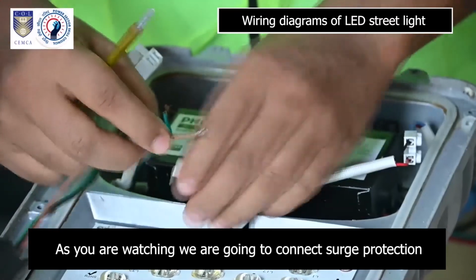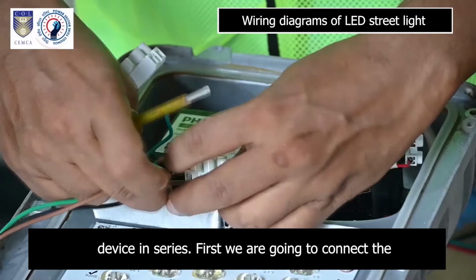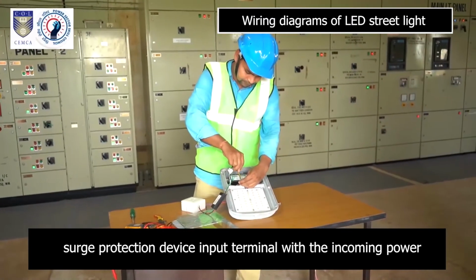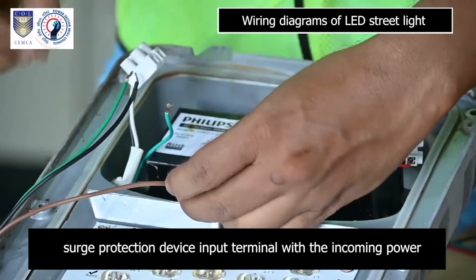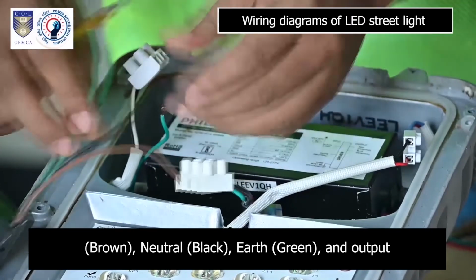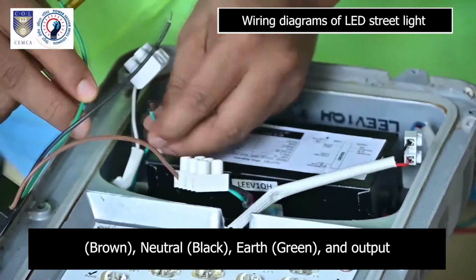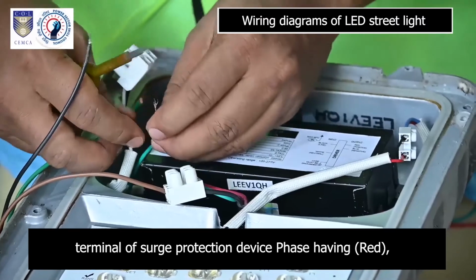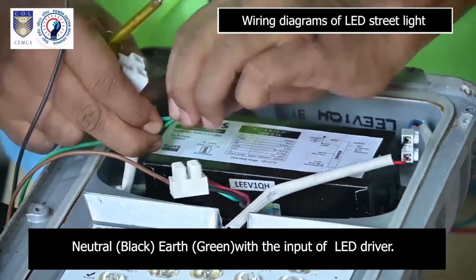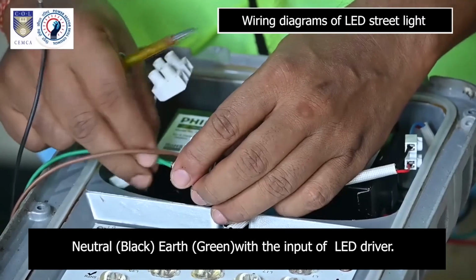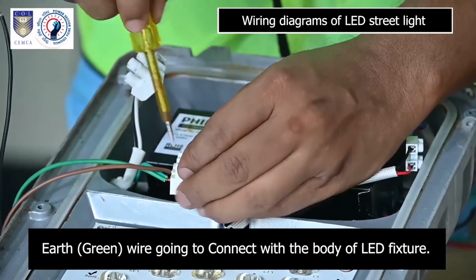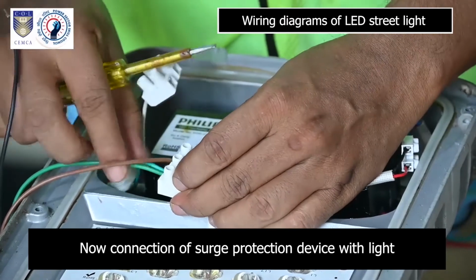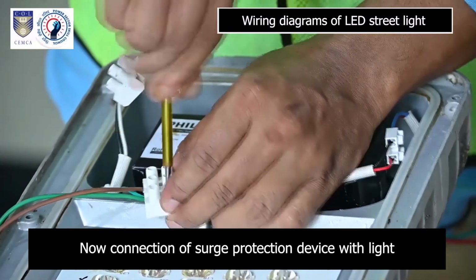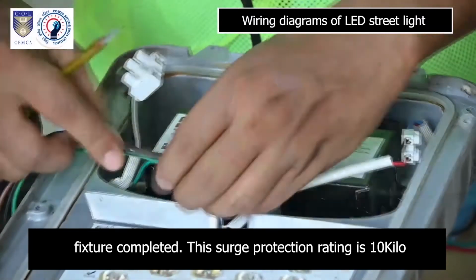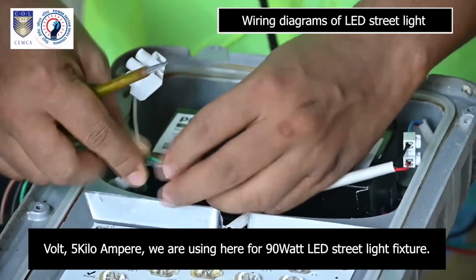As you are watching, we are going to connect surge protection device in series. First, we are going to connect the surge protection device input terminal with the incoming power supply terminal having 3-wire phase brown, neutral black, earth green, and output terminal of surge protection device phase red, neutral black, earth green with the input of LED driver. Earth green wire is going to connect with the body of LED fixture. Now, connection of surge protection device with light fixture is completed. This surge protection rating is 10 kV, 5 kA. We are using here for 90 watt LED street light fixture.